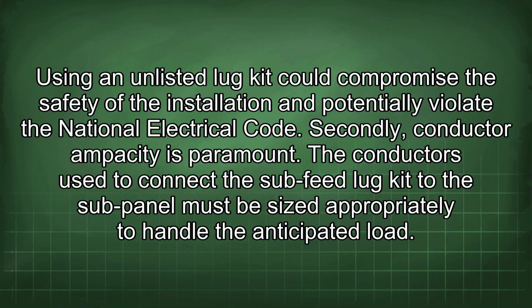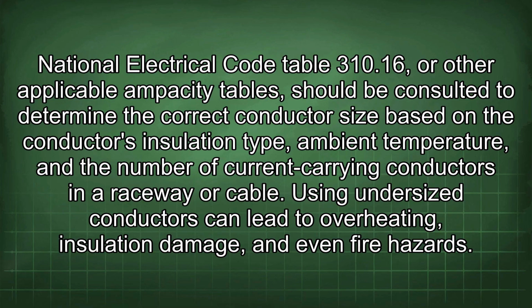Secondly, conductor ampacity is paramount. The conductors used to connect the sub-feed lug kit to the sub-panel must be sized appropriately to handle the anticipated load. National Electrical Code Table 310.16 or other applicable ampacity tables should be consulted to determine the correct conductor size based on the conductor's insulation type, ambient temperature, and the number of current-carrying conductors in a raceway or cable. Using undersized conductors can lead to overheating, insulation damage, and even fire hazards.